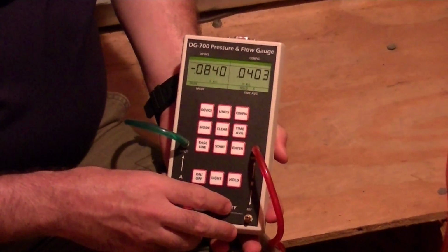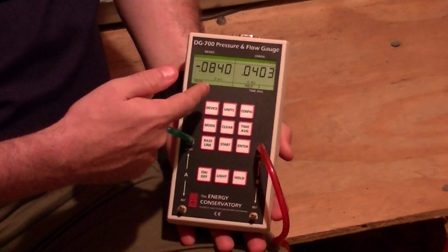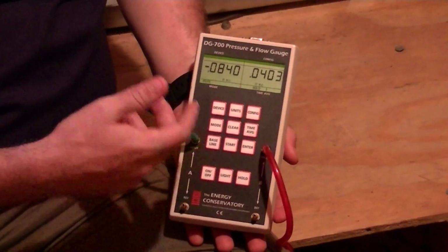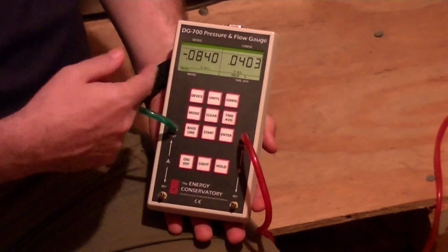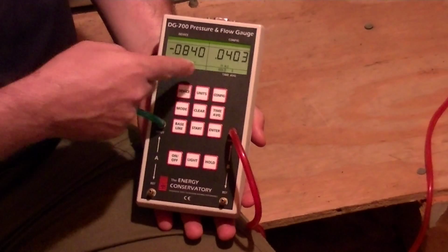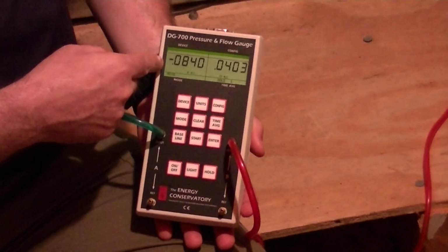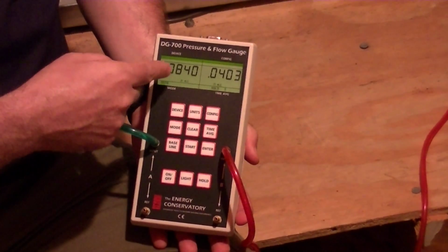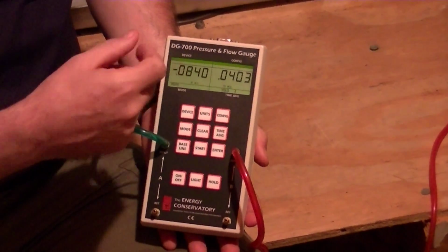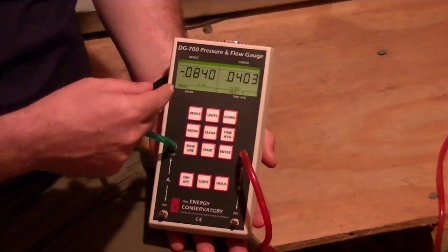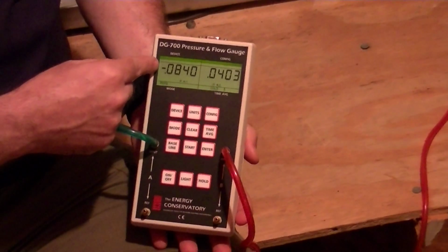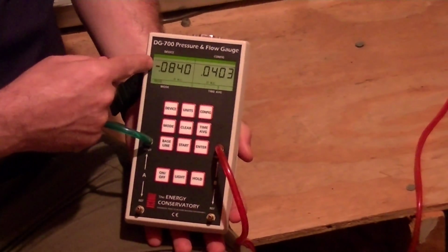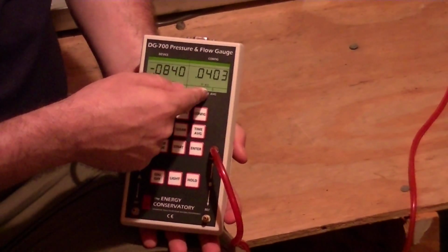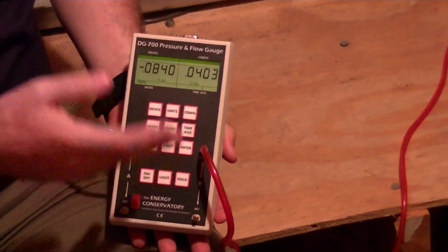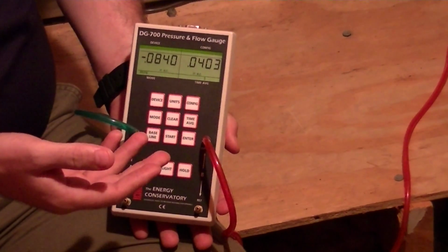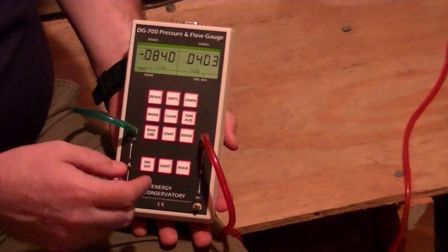There we go. You press the hold button, and it freezes the reading so that you can then set the gauge down, make your notes, and do the math. In this case, this gauge is telling us that we have 0.1243 inches of water column, 0.1243. Again, we ignore the negative sign over here, which is measuring the return side pressure, and we ignore any positive signs. We're just treating them as individual numbers with no positive or negative values associated with them.